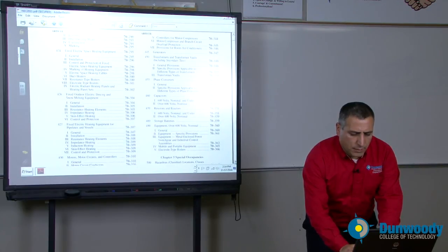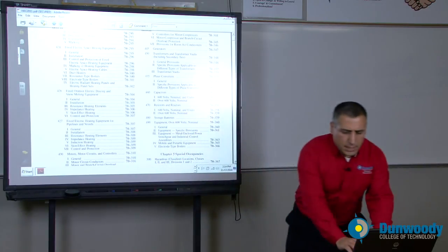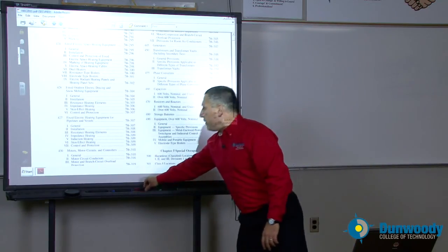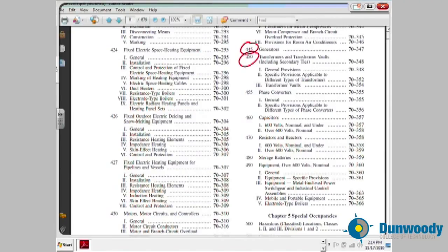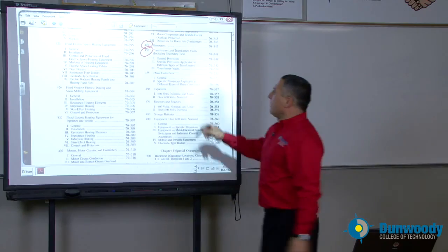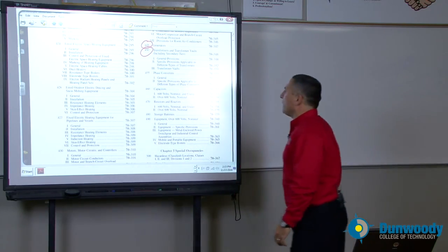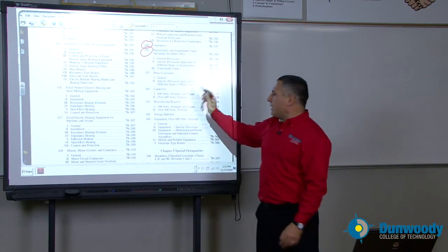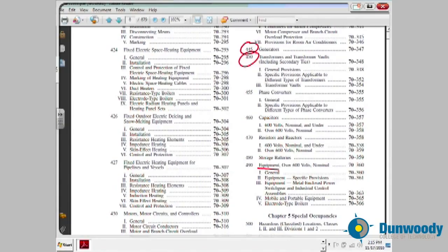Transformers and generators — if you have a generator, how do you size the overcurrent protection device and the conductor from the generator into the first overcurrent device? You're going to find this in article 445. Every respected building in the industry is going to have a 480/277-volt system that steps it down to 208/120. How do you install this transformer, and what's the largest transformer you can put without a transformer vault? Article 450. Advanced topics like capacitors, batteries, and equipment over 600 volts are for those going deeper into the NEC code book.